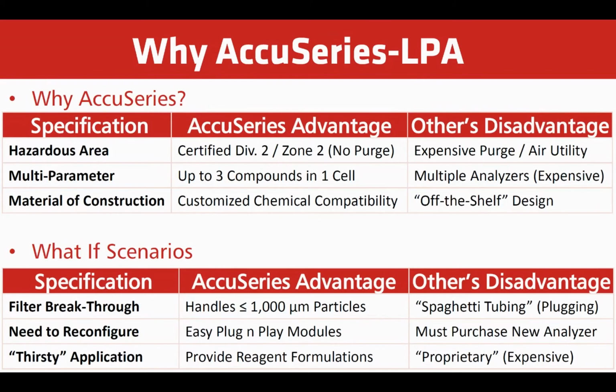Here we look at a couple of what-if scenarios. Well, if there was a filter breakthrough further up the line prior to the analyzer and some solids came, well, we already know that we have quarter-inch tubing, so it handles high amounts of solids in relatively large particle size without plugging up, as opposed to using tiny spaghetti tubing, or like to call it the 1/8 inch tiny tubing that'll plug up quite easily.